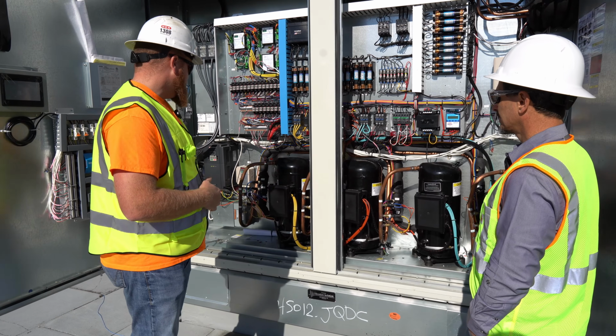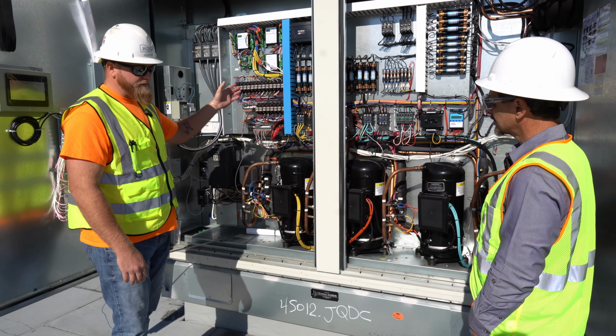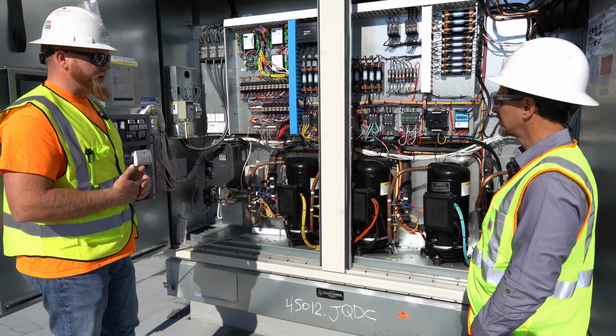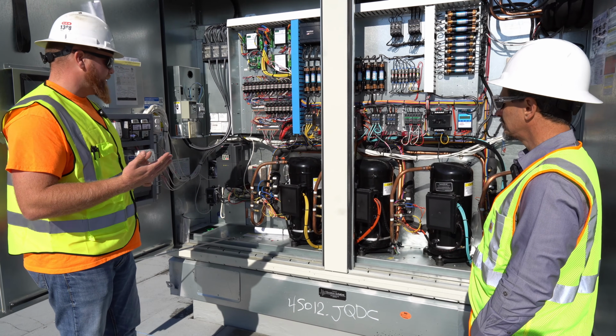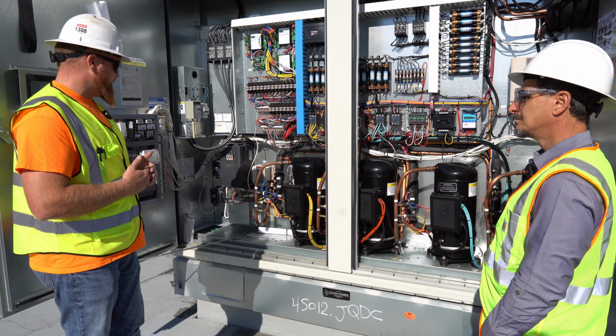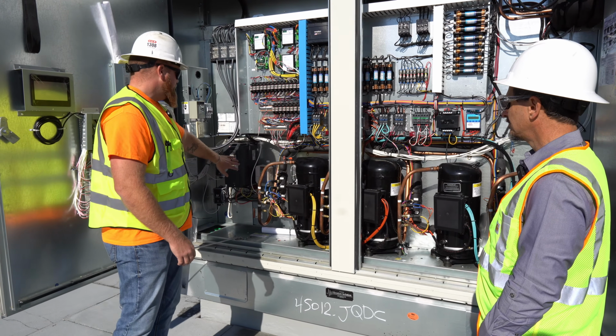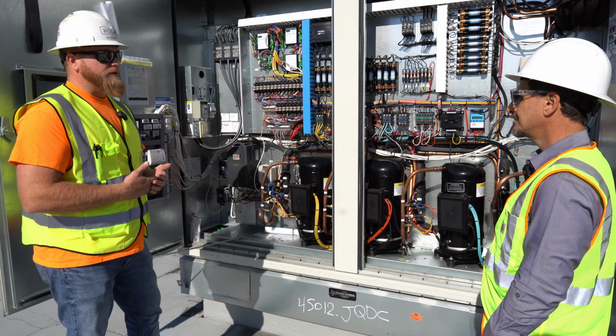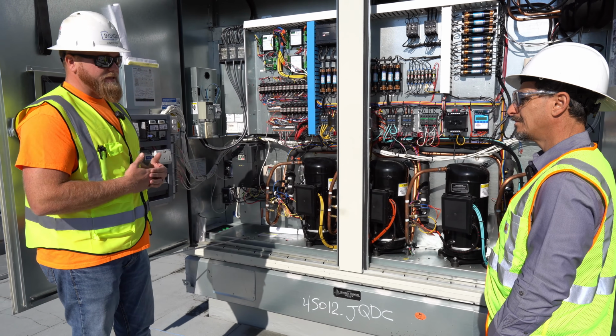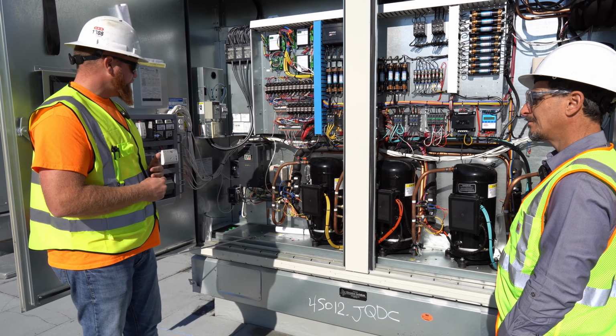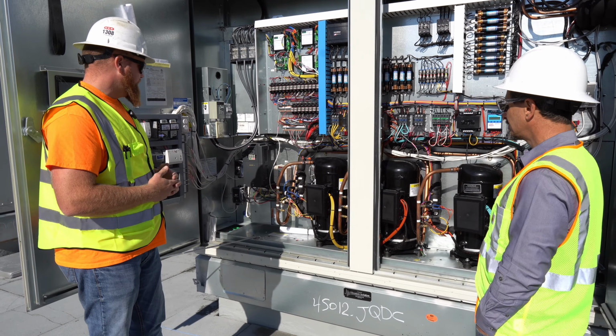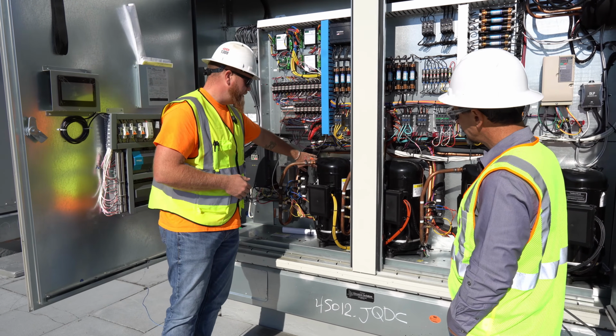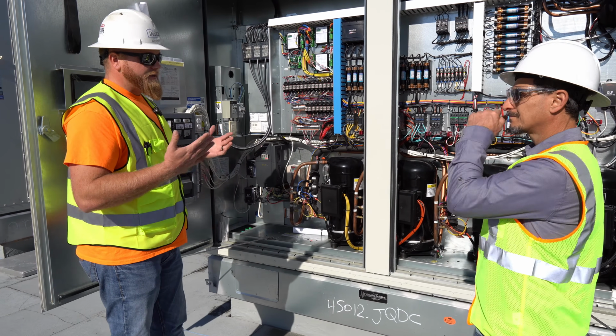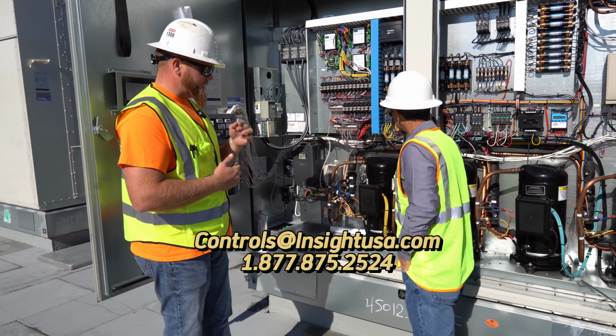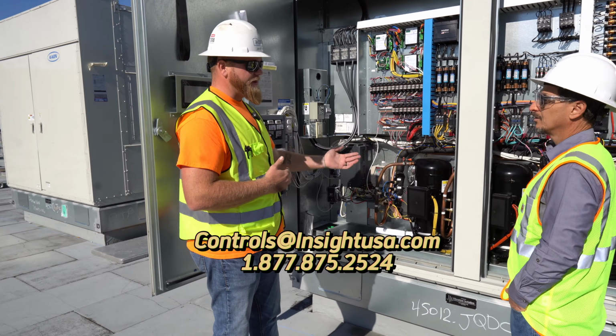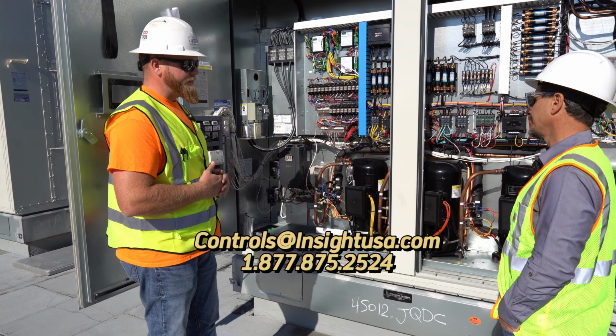Nice. Over here, we do have a VFD on the heat wheel for these systems, so we can drive them up and down based on our energy consumption and what kind of load we're trying to save off of those energy recovery wheels. This will be the exhaust fan VFD. That will be controlling our exhaust duct static or space pressure control. Again, another variable VFD. This was the high pressure switch that we were talking about. If anything exceeds whatever the set point, I believe at this project it's somewhere around the 4-inch range, that'll be the automatic reset safety.